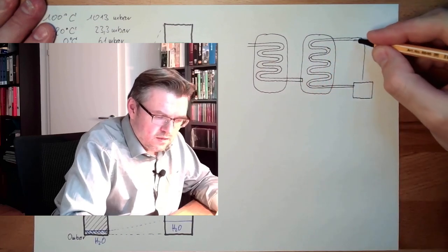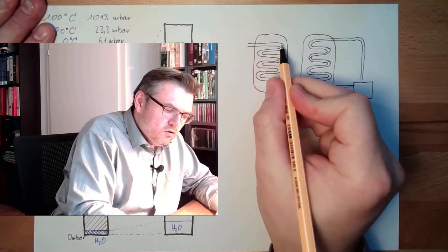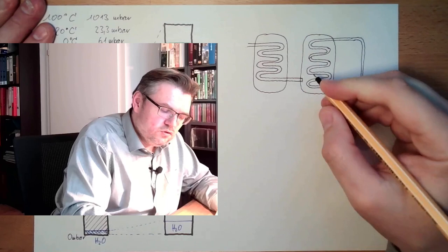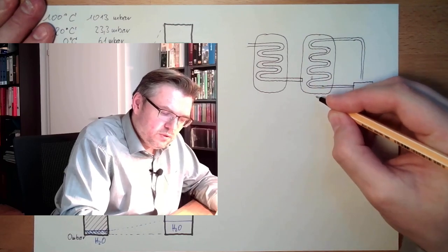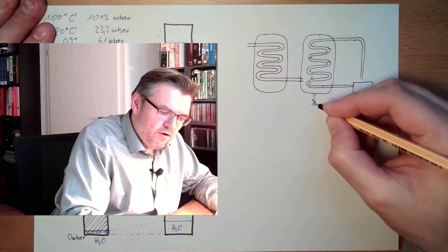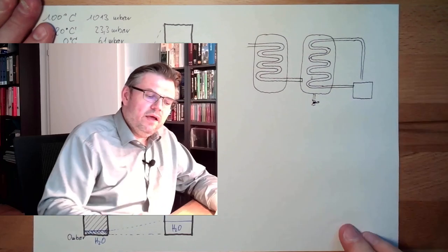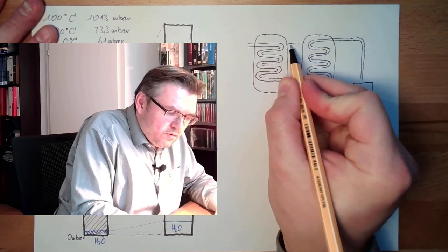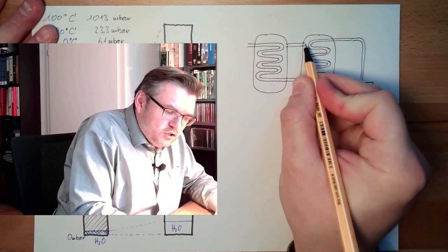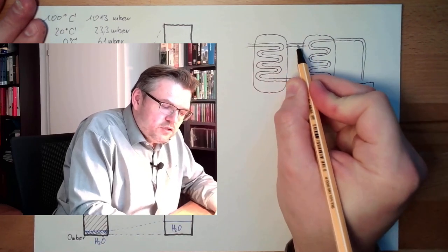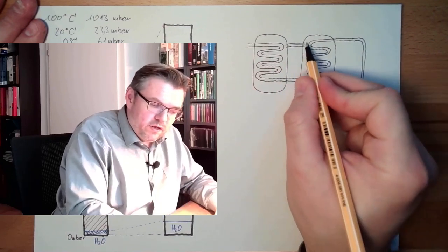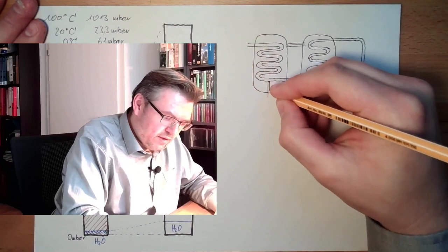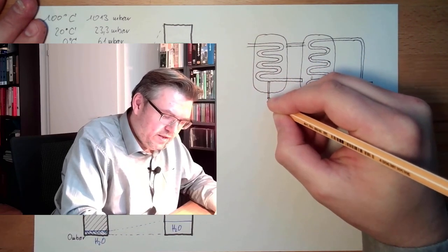It's like in the cold beverage. Here the hot steamy compressed air is coming inside, and here are cool lines, and on those cool lines there will be drops, and these drops will go down, and underneath here I have somewhere a valve, and I can open and close it and get rid of the condensate. Okay? And here then I go out again. Here is partially dry air. And this partially dry air, which has been already cooled, will already cool this here as well. And here I might have some condensate already inside.